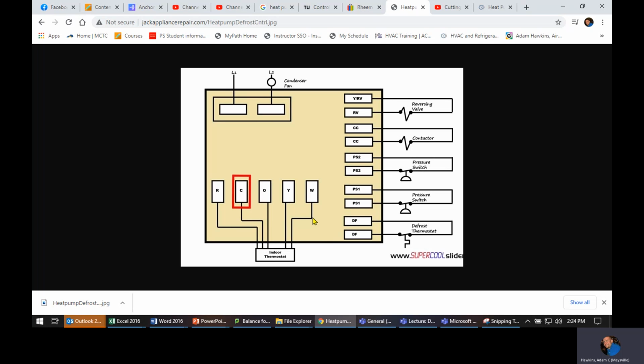So when it goes into defrost, the first thing that has to happen is orange will switch positions. Simultaneously, orange switches position, sends the unit to cooling. The condenser fan drops out. So up here, W energizes by sending power from red in the board over to W. That W sends a back signal back to the indoor unit, bringing on the heat strips.